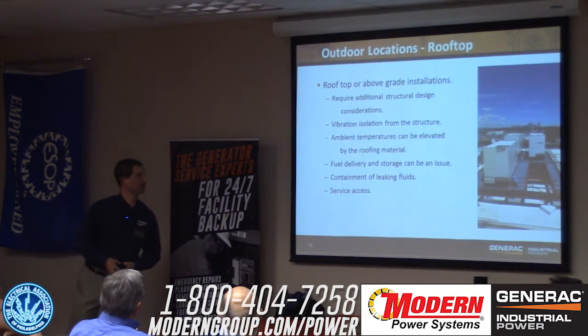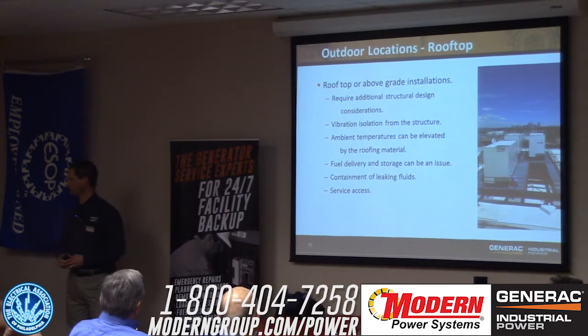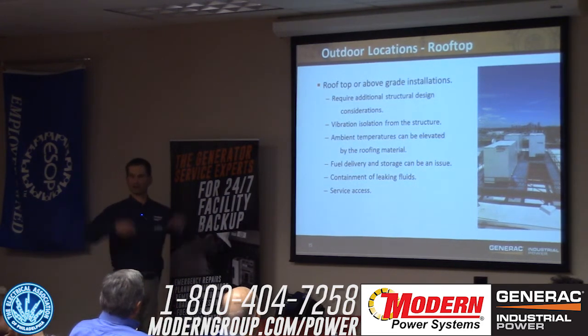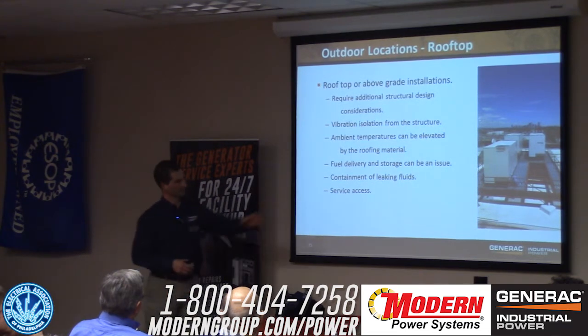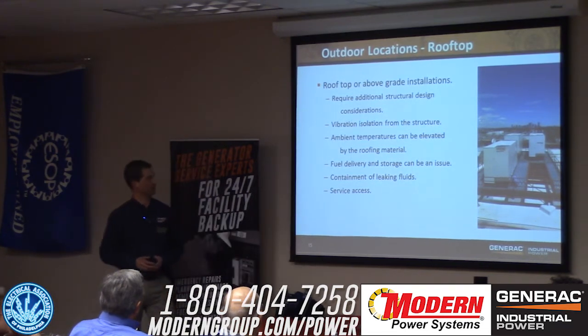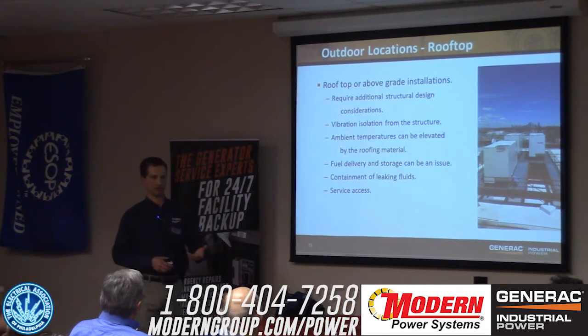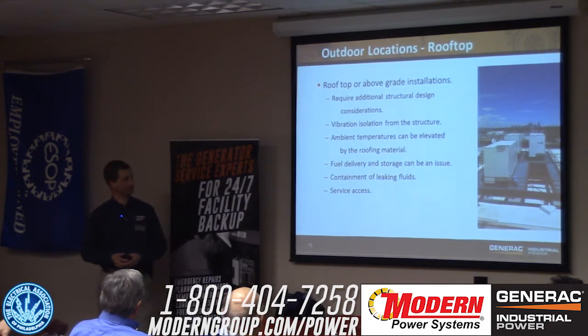Rooftop installations have some different requirements too. You've got to make sure the generator stays on the roof and doesn't end up on the floor below, so there will be structural upgrades needed. Depending on who's below—if it's residences—you may need vibration isolation. Again, this is something the engineer takes care of, putting vibration isolators in the design if needed.